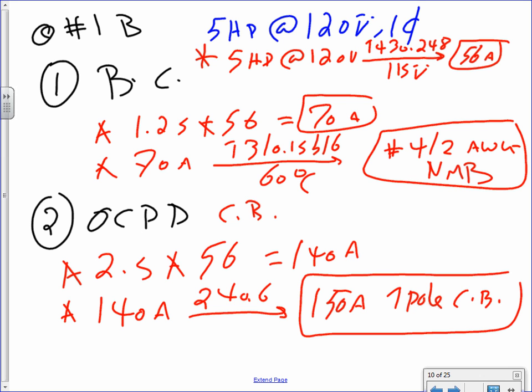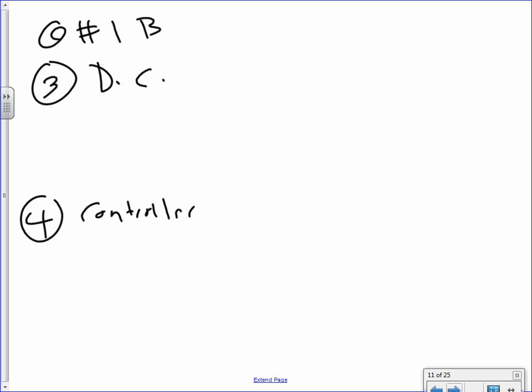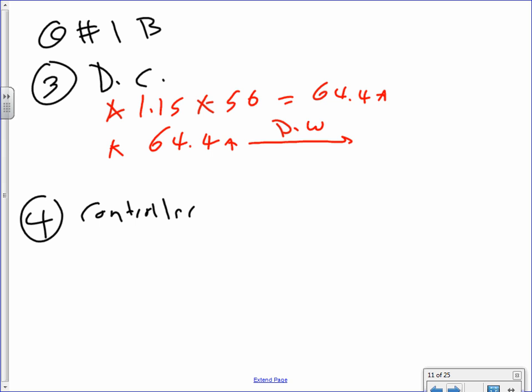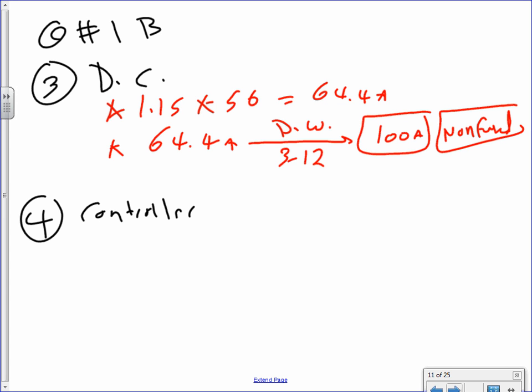Should we go to the disconnect when you guys are ready? Disconnect. Same thing, I'm repeating myself here. So the disconnect is 1.15 multiplied by 56. That will get you 64.4 amp. And then you take the 64.4 amp, take this one to table 312, and that will get you 100 amp, 100 amp non-fused. It has to be 2-pole here, but we use only 1 pole.